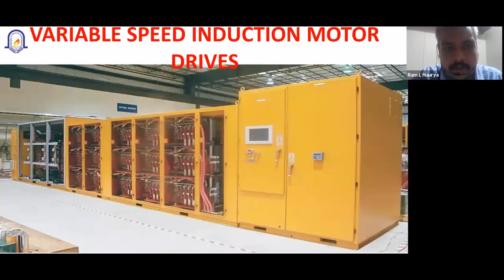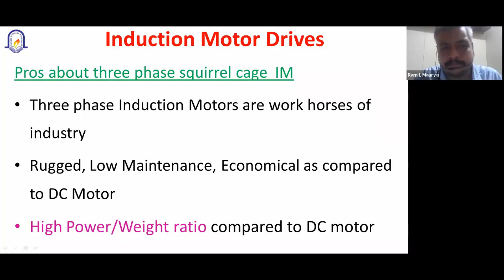These are three-phase induction motors. The advantages of a three-phase induction motor are that, as compared to DC motors, they are very rugged, low maintenance, economical, and they have a higher power to weight ratio than DC motors. But there are some cons. Speed control of a DC motor is very easy, but a DC motor is costly. Speed control of an AC induction motor is not easy, so it requires V by F, vector control, and all those things.